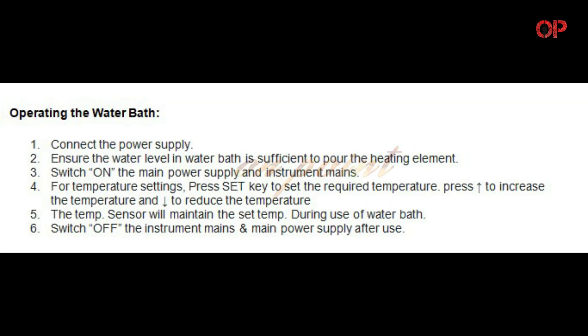Operating the Water Bath: 1. Connect the Power Supply. 2. Ensure the water level in the water bath is sufficient to cover the heating element. 3. Switch on the Main Power Supply and Instrument Mains. 4. For temperature settings, press the Set Key to set the required temperature. Press the Upward Arrow to increase the temperature and Downward Arrow to reduce the temperature. 5. The Temp Sensor will maintain the set temperature during use of the water bath. 6. Switch off the Instrument Mains and Main Power Supply after use.